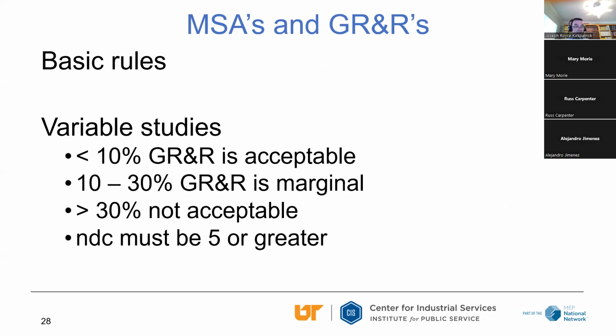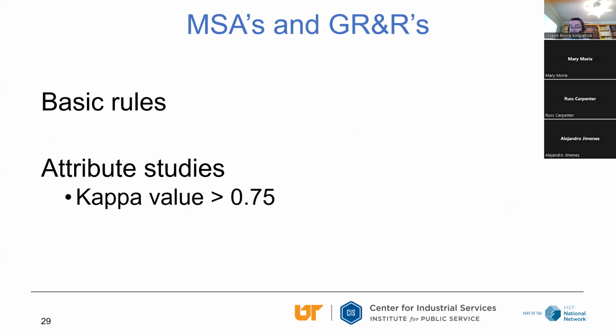Basic rules of MSA studies: they need to be less than 10% if they're variable gauge R&Rs, meaning you have a number that you're addressing. 10 to 30% is considered marginal, depending on the use of the gauge and the risks. Greater than 30% is not acceptable. And the number of NDCs, the number of distinct categories or buckets that your samples come from, needs to be 5 or greater. If your NDC is less than 5, your study's invalid. It's not considered acceptable. The basic rule for attribute studies is the kappa value, which has to be greater than 0.75.